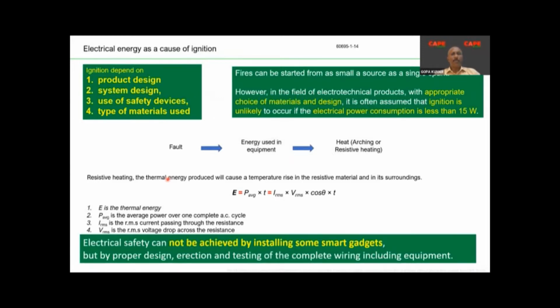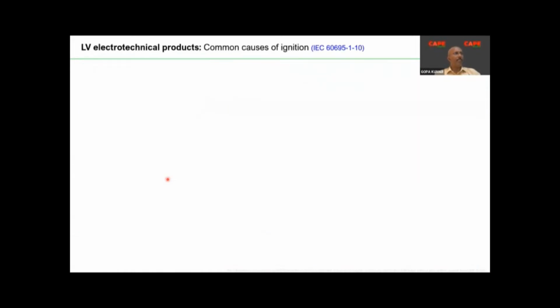I will explain some of the standards with respect to fire in an electrical apparatus. But before that, you must understand that electrical safety cannot be achieved by installing one gadget. Because in the market, if you look, there are devices coming, smart devices, IoT-based devices. If you buy one and put it in your line, you get rid of all the electrical fire problems. These are absolutely not possible. So electrical safety, or fire from ignition of electricity, can be achieved only by proper design, proper erection, system design, use of safety devices, and type of materials.